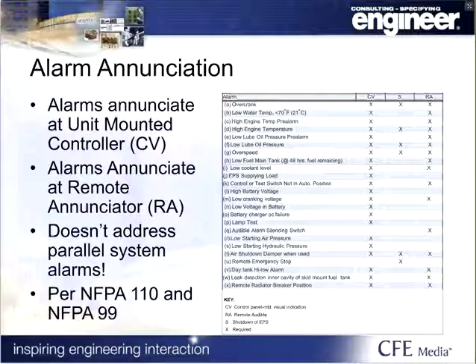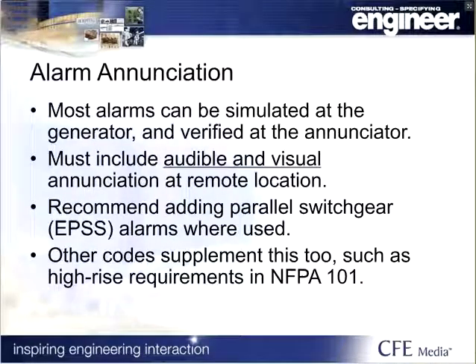So basically, on this list, if it says RA, there'll be an alarm that has to annunciate at an intended location within the building. Most of these alarms can be simulated from the generator or the parallel switchgear. And you can maybe do a jumper, or the generator manufacturer can be out there to simulate certain alarms in the field. And you need to do it sequentially, go through them all, and make sure that they annunciate at that 24-hour location.